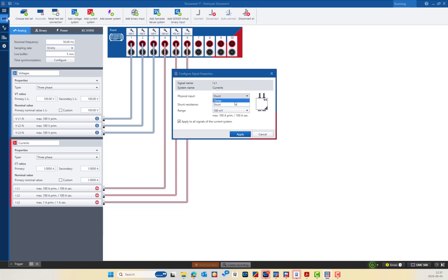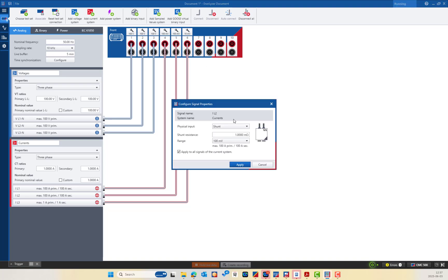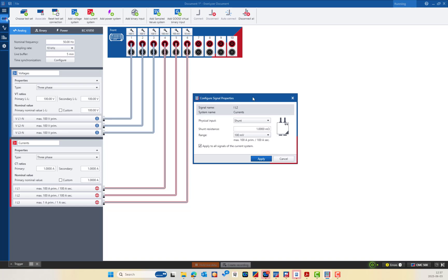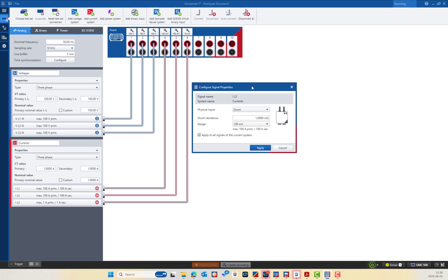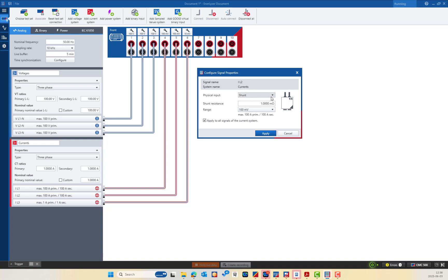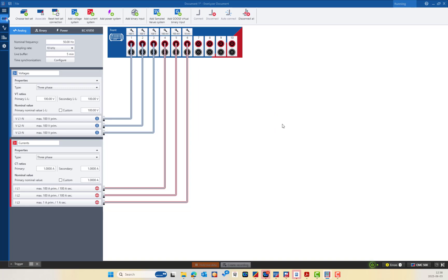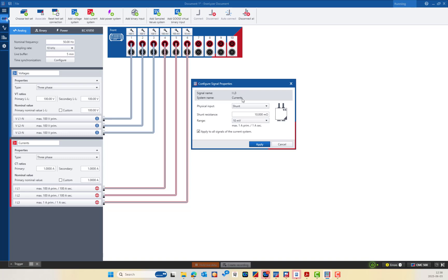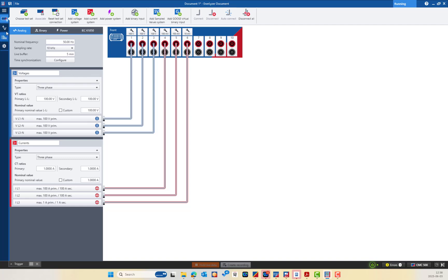There is also a clamp option where you define the clamp ratio and nominal range. For analog input 5 (IL2), I use a 1 milli-ohm shunt with a 100 mV range. For analog input 6 (IL3), I use a 10 milli-ohm shunt with a 10 mV nominal range. Importantly, in the CMC 500 each analog input has an individual potential group, so there is no need to segregate inputs as 5, 7, 9 like in the CMC 356 — each input can be used individually.